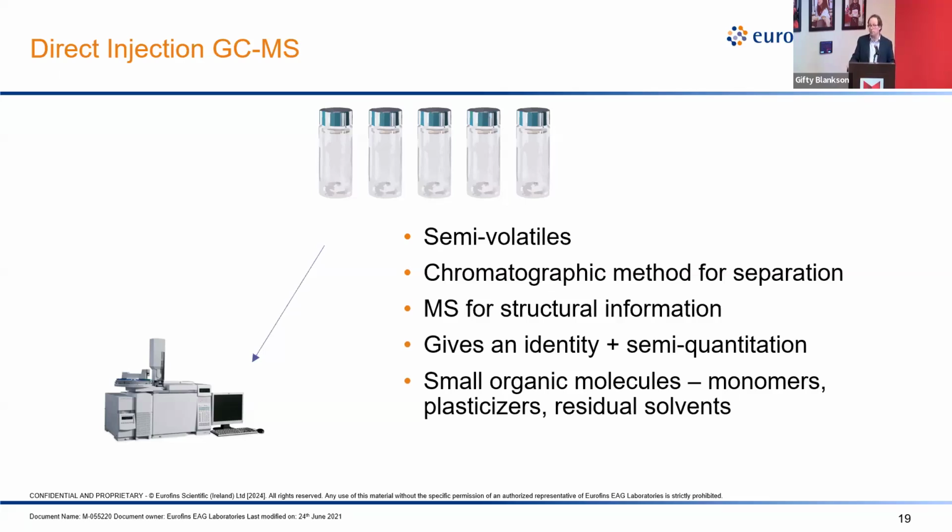And that's important because some of them can be a problem. Some of you may have heard stuff about acrylates, consumer products. That's kind of a current thing. And that's one example. Those acrylates are leftovers from the manufacturing process. They're monomer, and they're not biocompatible. They cause contact dermatitis. So it covers monomers, also some plasticizers.